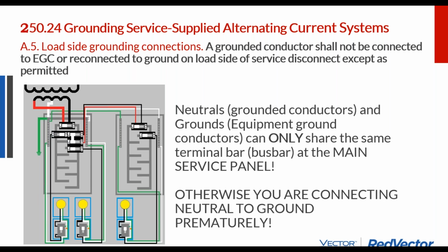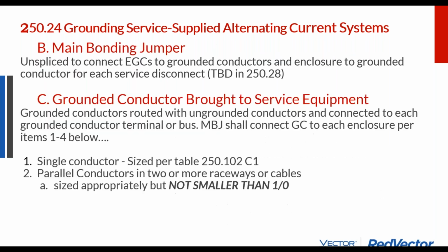So this is the biggest kind of safety mistake that an amateur or beginning solar installer can make. They install the solar disconnect switches. It says you need to have a main bonding jumper connecting the neutral to ground. You need to take a step back and say, well, wait a minute, does one already exist there or not? So they say that neutral to ground connection is called the main bonding jumper.